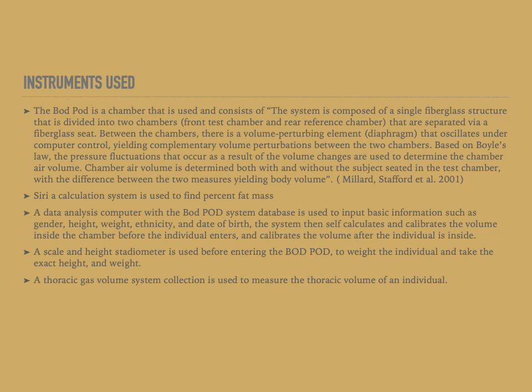The BODPOD comes with its own system of calculations using the Siri equation to find the percent fat mass. It also comes with a data analysis computer — a database used to input basic information such as gender, height to the nearest centimeter, weight in kilograms, and ethnicity. It's very important to input the correct ethnicity, as different ethnicities can cause over- or underestimation in percent fat mass. For example, white versus African-American counterparts may have a difference in percent fat mass. The date of birth is also used to log the individual and keep records using age.